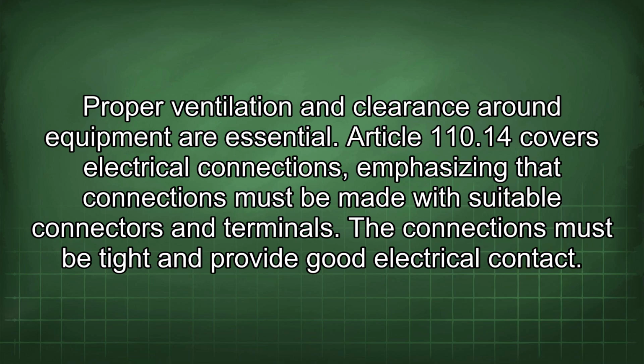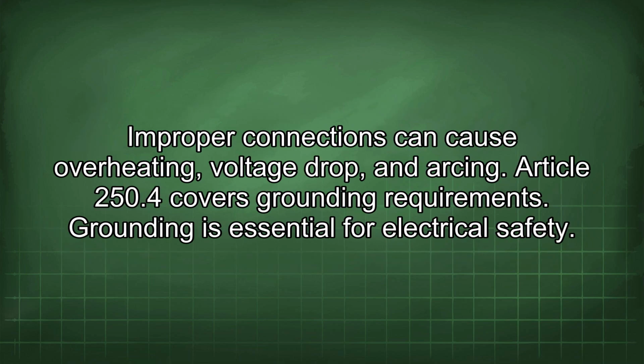Article 110.14 covers electrical connections, emphasizing that connections must be made with suitable connectors and terminals. The connections must be tight and provide good electrical contact. Improper connections can cause overheating, voltage drop, and arcing.